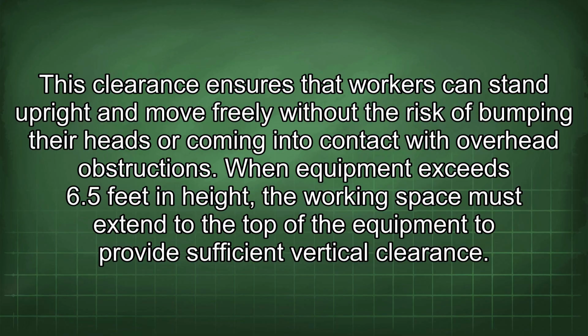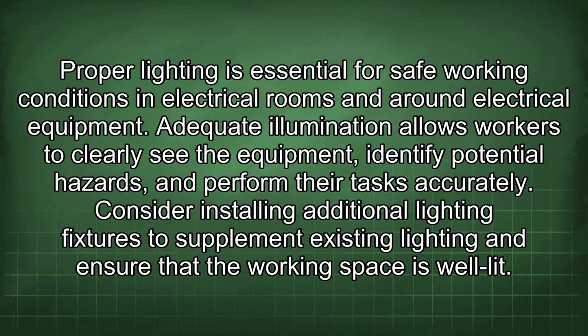When equipment exceeds 6.5 feet in height, the working space must extend to the top of the equipment to provide sufficient vertical clearance. Proper lighting is essential for safe working conditions in electrical rooms and around electrical equipment. Adequate illumination allows workers to clearly see the equipment, identify potential hazards, and perform their tasks accurately. Consider installing additional lighting fixtures to supplement existing lighting and ensure that the working space is well lit.